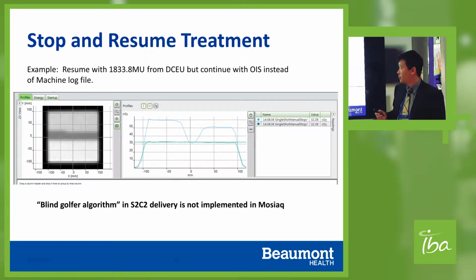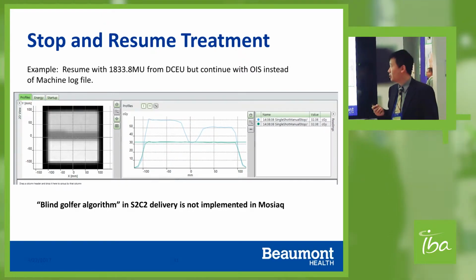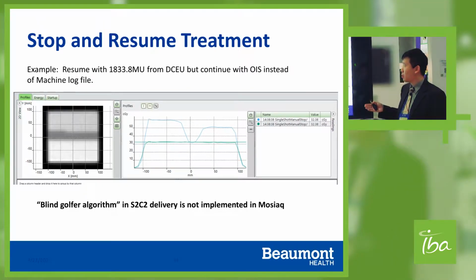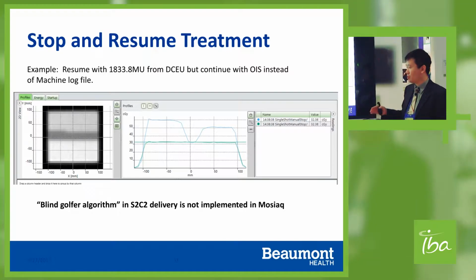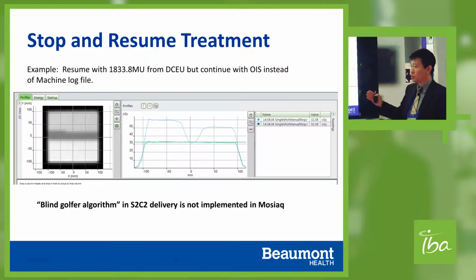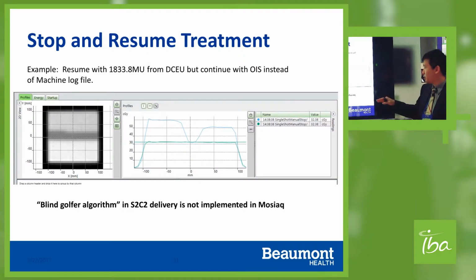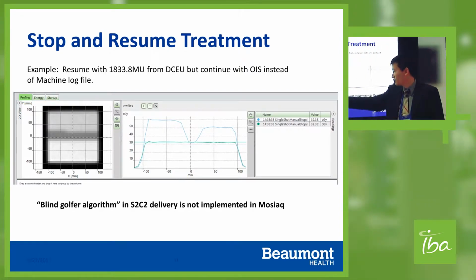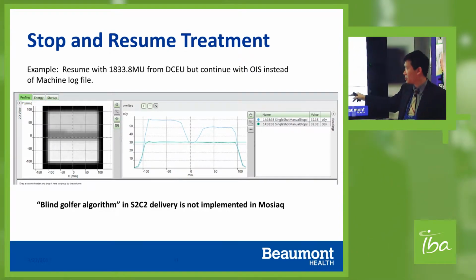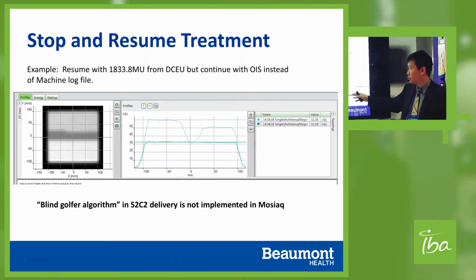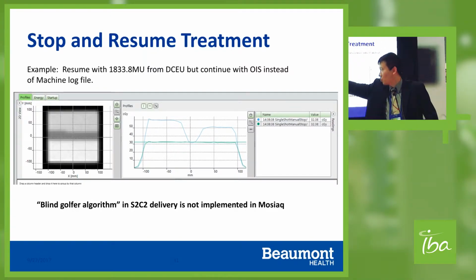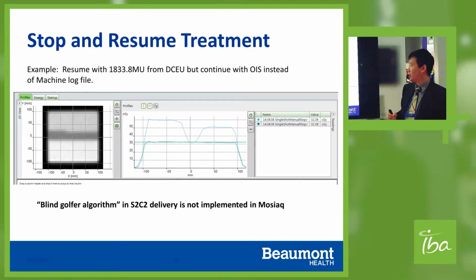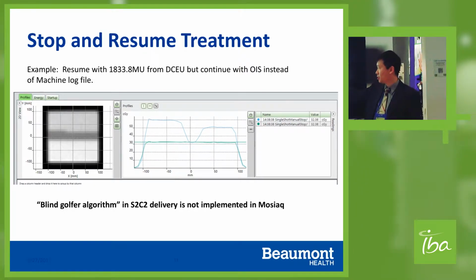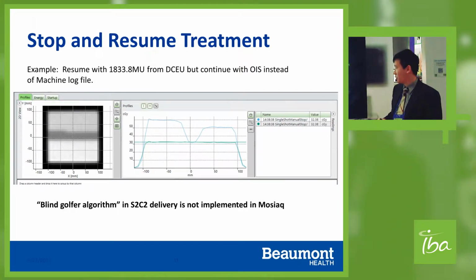So this is one example: the Proteus One integration with Mosaic doesn't work quite well in the stop and resume treatment. When the machine stops, you cannot resume from the Mosaic part. This is mainly because the algorithm from the S2C2 delivery is not implemented into the Mosaic OIS, which causes the resume to skip one layer or a couple of the energy scans. So that's one potential safety issue. This has already been opened as a bug with Mosaic, and IBA is working with the Mosaic team to implement the safety fix.